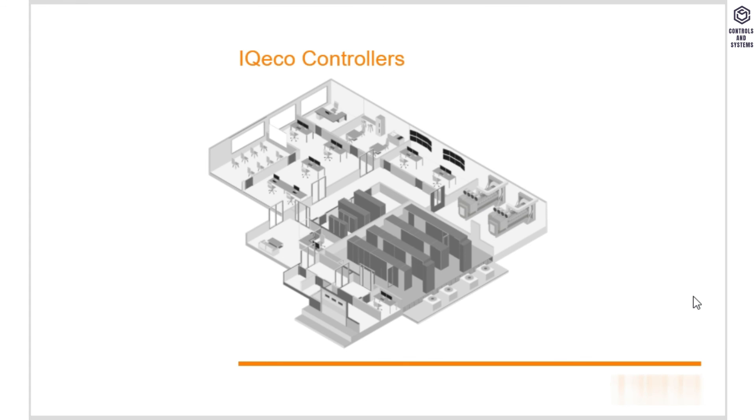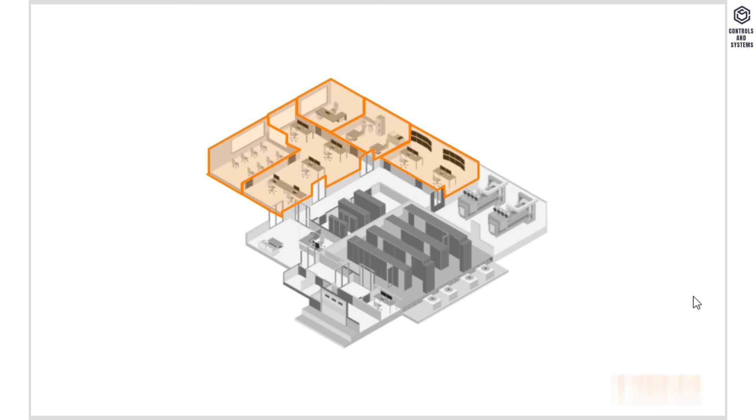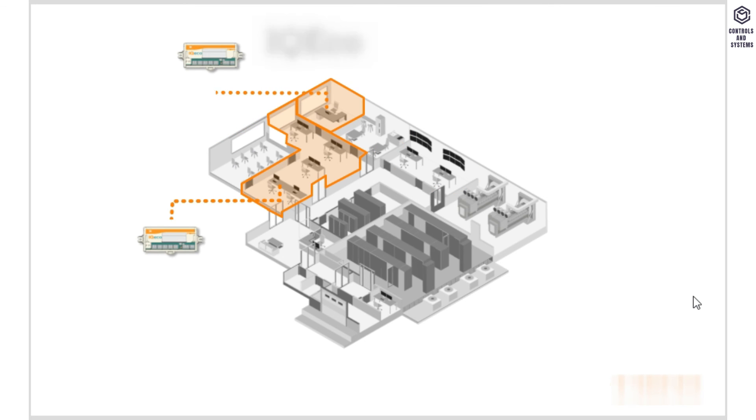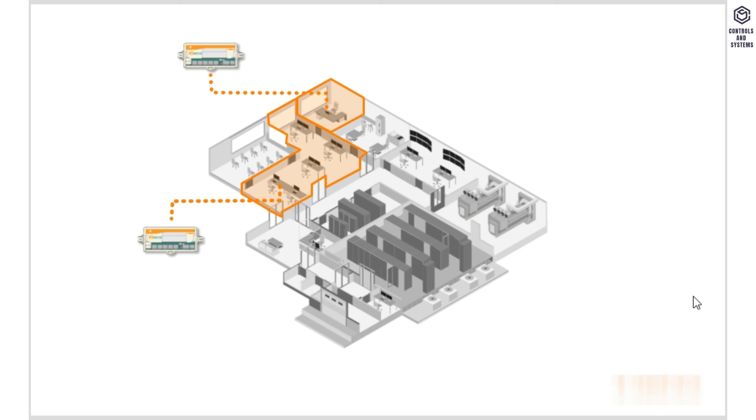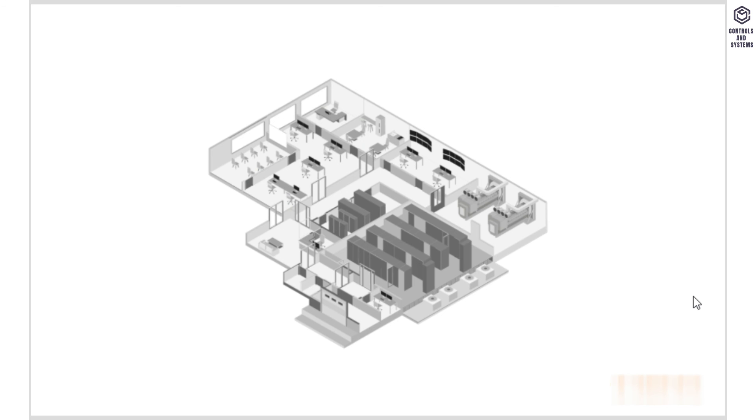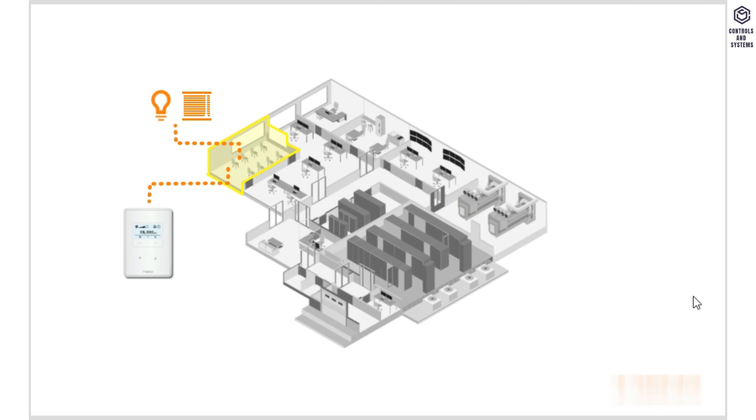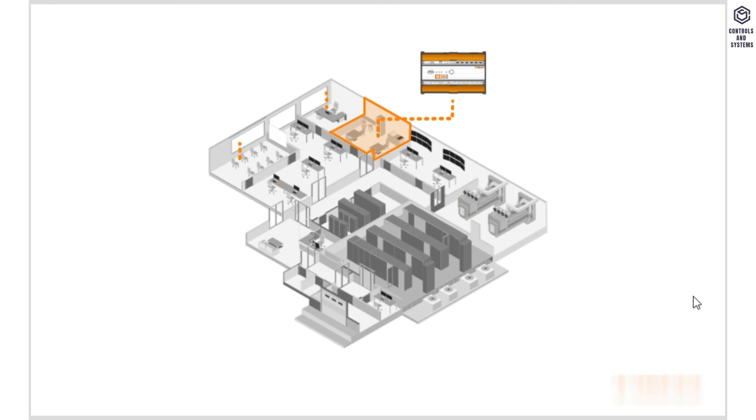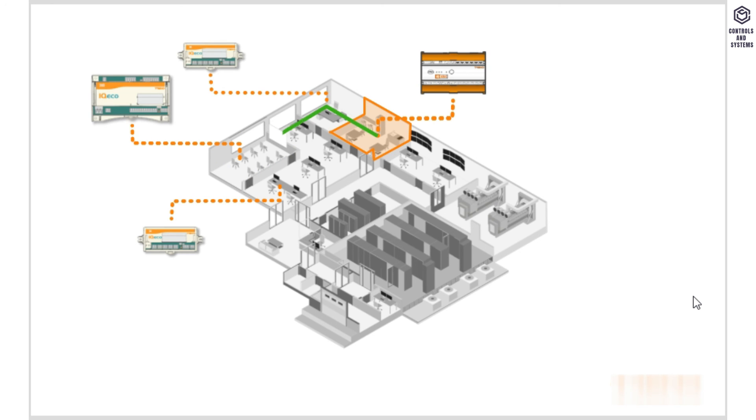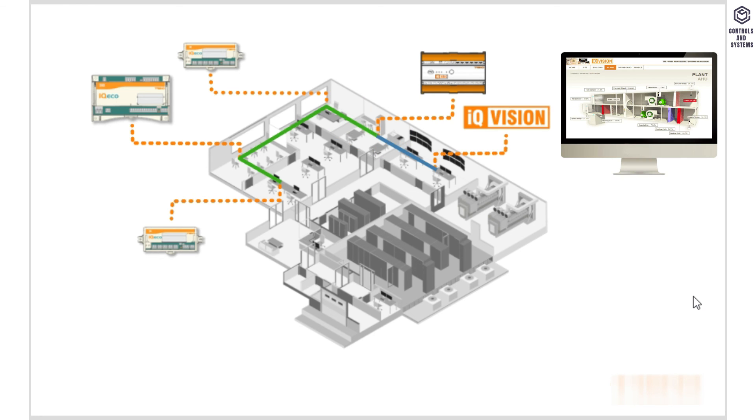In the offices of our data center, we have two types of IQeco. There are IQeco-31s which are controlling identical fan coil units, so therefore they have the same strategy installed. We also have an IQeco-38 which has a unique strategy for the meeting room, which includes control of the lighting and blind in the room along with a local room display. As we have an IQ4NC in place connecting them all to the rest of the network, they can still be seen and controlled by the central IQ Vision for the site.